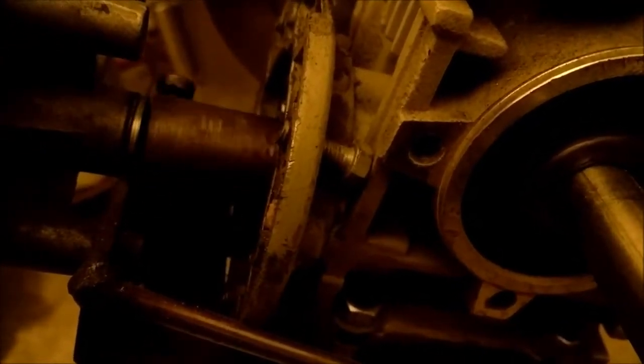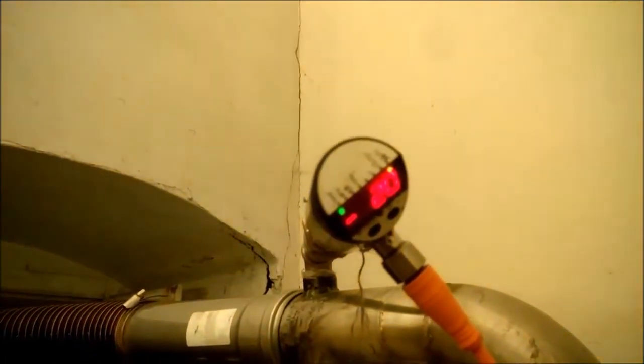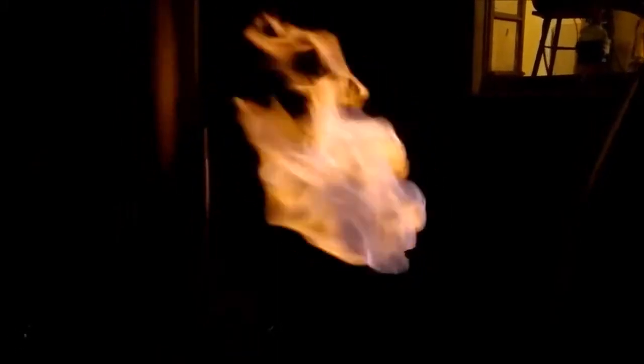If we have a look at the under pressure sensor, we see it is always at its set point. If the agitator is working, the flare has much less quality. You see there's a huge amount of charcoal dust that comes free and it colors the gasifier flare.